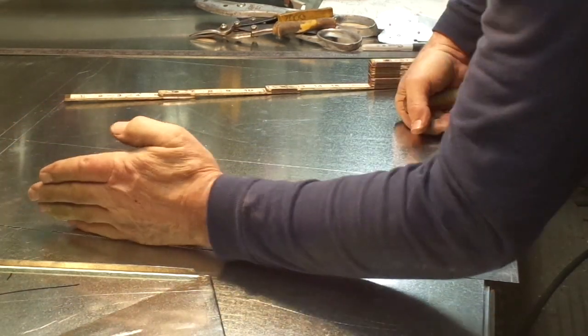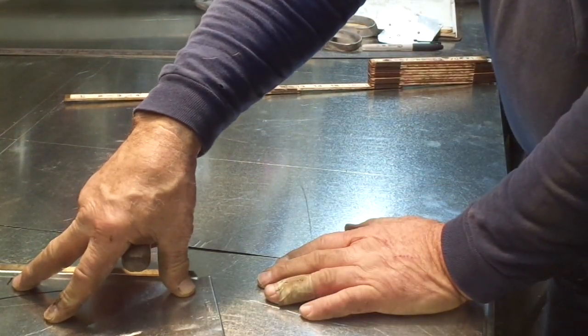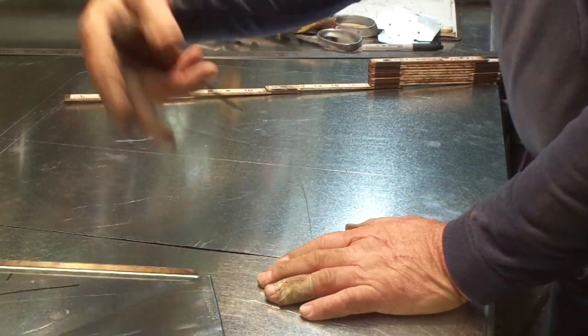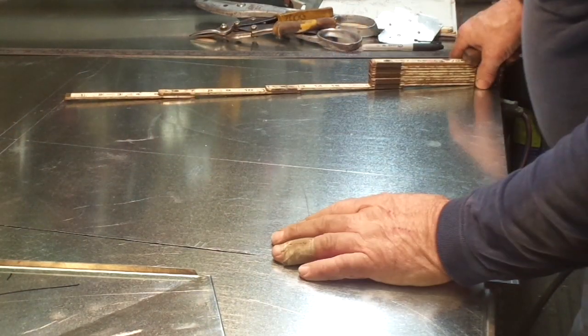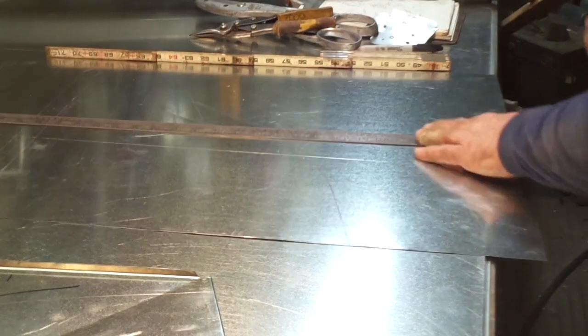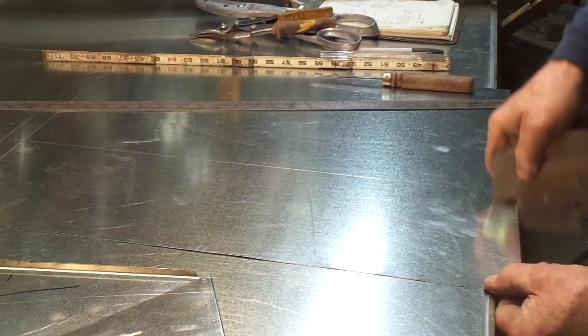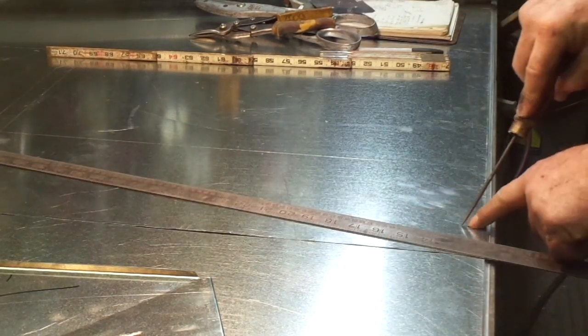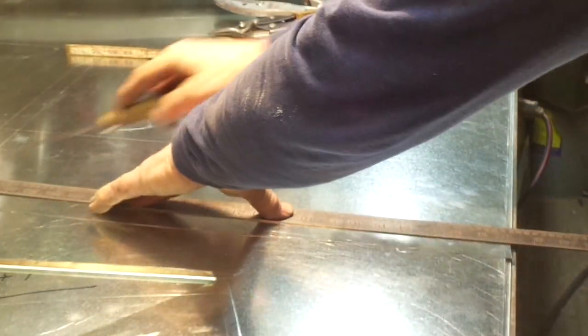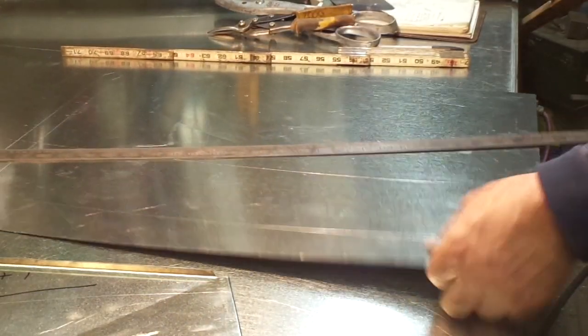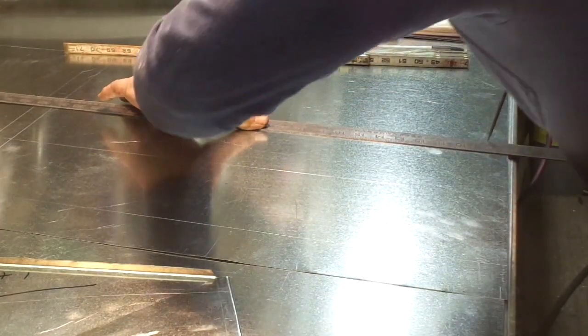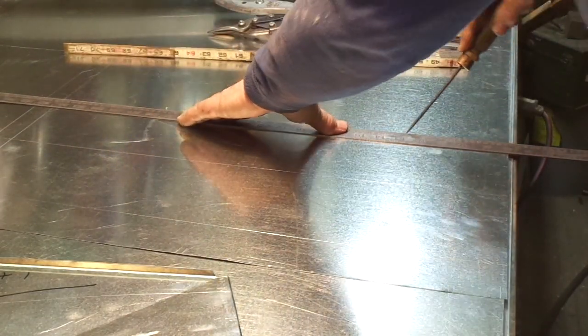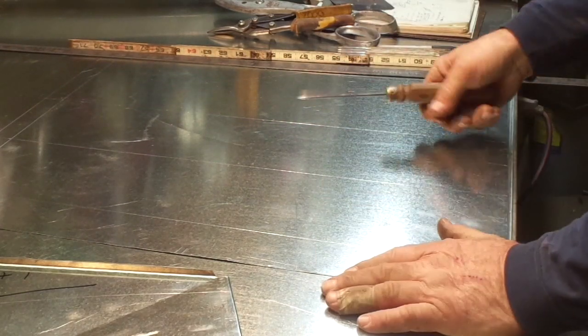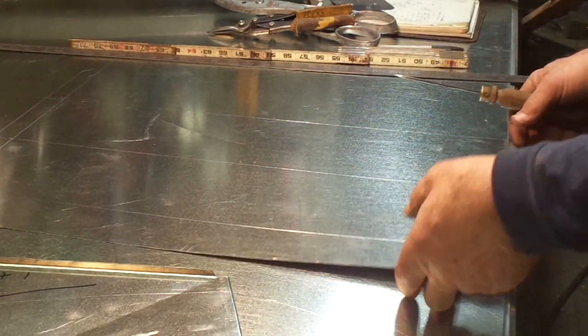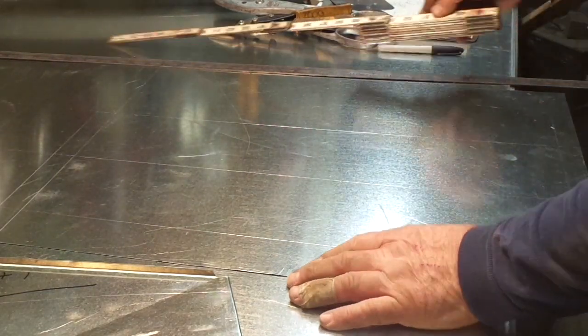You can do it squarely off of one side, but then you have a different type of duct. It's much more difficult to make because you have additional measurements, but it's much easier to make an equal taper transition when possible right here. So now we're going to put up a 1-inch drive down here on the bottom, and off of that intersection, the intersection of those two drive lines, we go up to here. It's just going to be a subtle change in angle, but enough to where it's going to be 3/4 inch over the course of 24 inches. So we're really only driving in 3/8 of an inch on either side. It's a very subtle change in dimension, but enough to where you don't want to have to make that connection with duct tape. Ain't nothing worse than duct tape on a piece of duct.